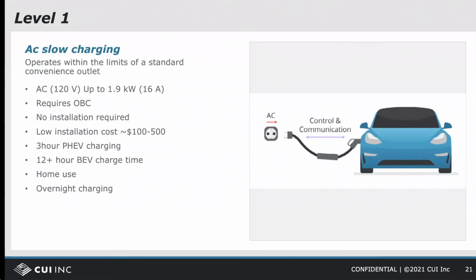Level 1, sometimes called AC slow charging, is the lowest and slowest power level. With this level, the EV plugs into a standard 3-prong outlet, just like you'd plug in any home appliance. For the IEC, this is similar to their Mode 1, but the IEC specifies either a single-phase voltage limit of 250 volts or a 3-phase limit of 480 volts. The power is limited by the current rating of the outlet, which is 16 amps in the North American case, and makes it the slowest charging level. For the NEC and SAE, level 1 has a max rating of 1.9 kilowatts, while the IEC limit is 4 or 11 kilowatts, depending on whether the source is single or 3-phase.